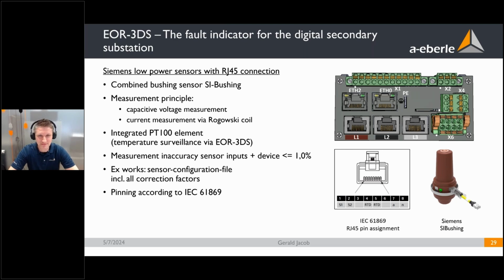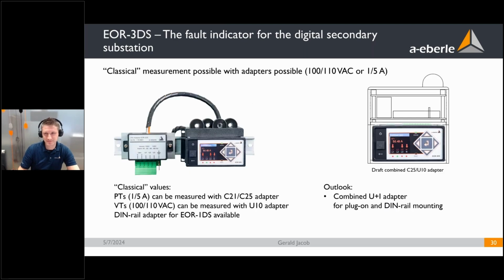that you have to configure in each device so that the sensors measure perfectly. With the Siemens SI bushing, you don't have to care about that, because they upload such a sensor configuration file on the device, and the device automatically takes these correction factors into account and measures perfectly from the first minute. So you don't have to parameterize anything. You don't have to insert all these 12 correction factors per device. So very, very user-friendly from my point of view.